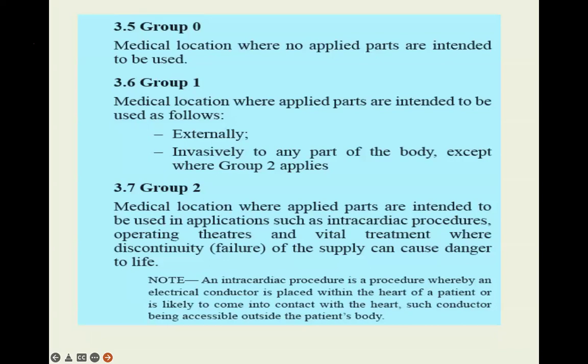Group 0 is a situation where no applied parts are used in the medical location. Group 1 is where medical parts are applied to be used externally or invasively to any part of the body. And group 2 is the medical location where applied parts are intended to be used in applications such as intracardiac procedures, operation theaters, and vital treatment, where discontinuity of supply can cause danger to life.